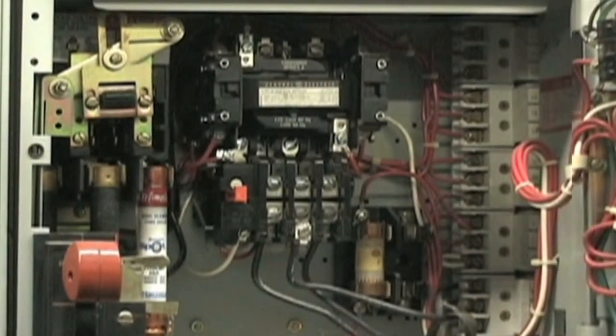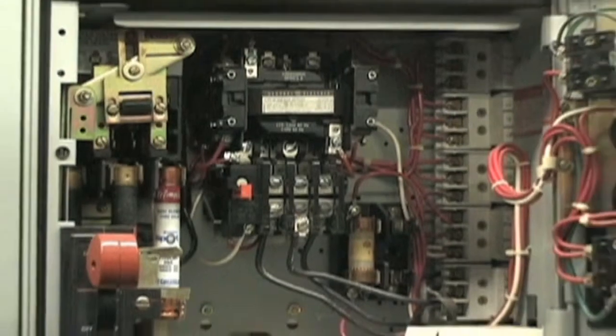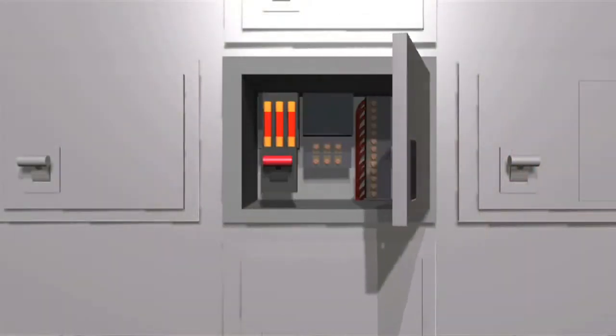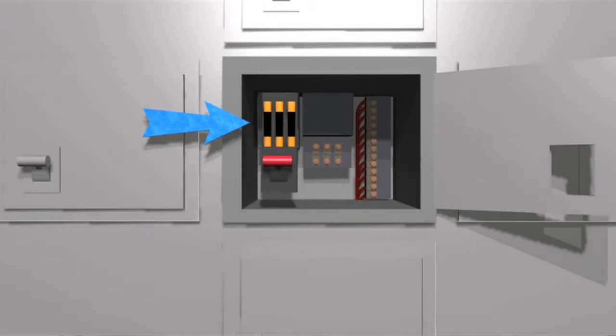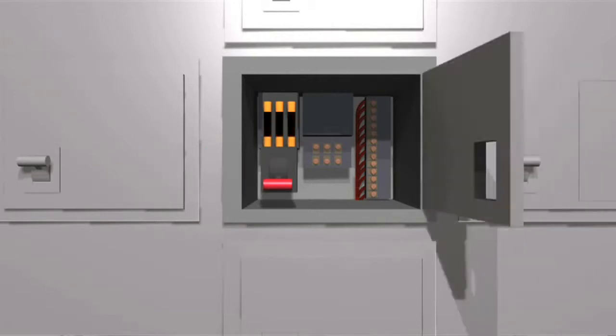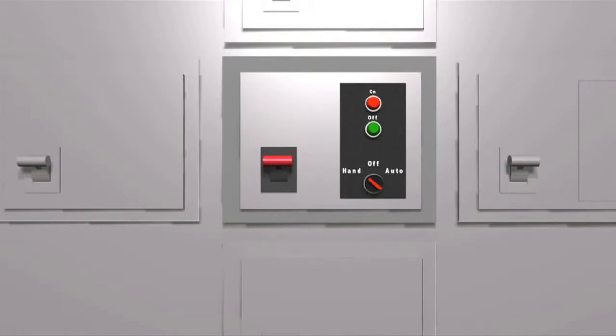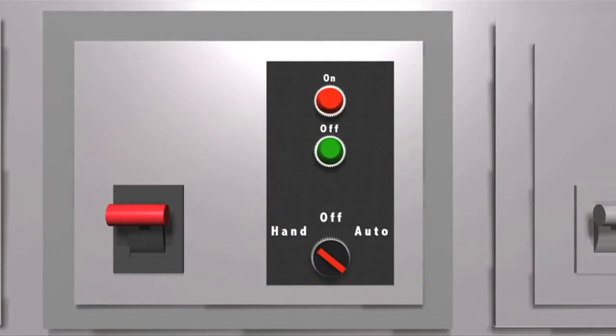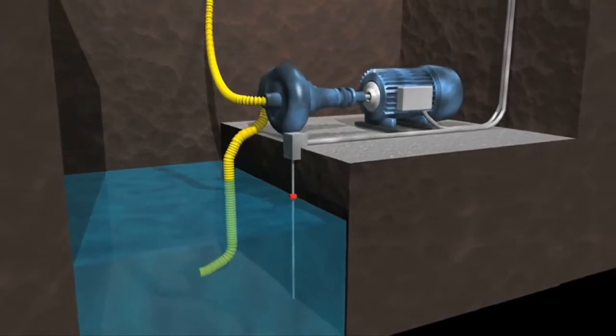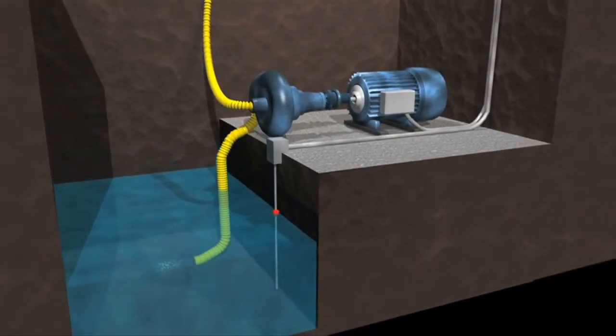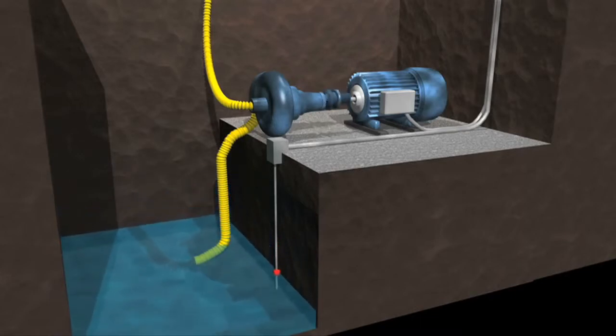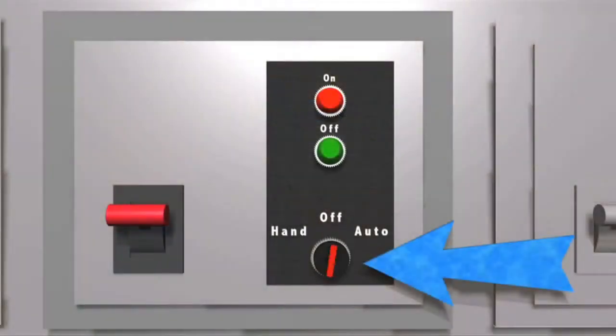For the purpose of electrical distribution, we only need to focus on a few components that relate specifically to the electrical. Each bucket has a disconnect switch and a breaker. The breaker is designed to trip if the power exceeds the recommended setting. The disconnect switch is there to manually turn off the power to the motor. There is also a combination motor starter. These consist of the same disconnect switch and breaker, but also has two other features. It has a start-stop switch to manually turn the motor on and off. It also has a hand-off auto switch. When this switch is in the auto mode, it allows another source to control the motor. A good example of this would be a sump pump. A float switch that is switched on by rising water will control the sump pump. The motor will be turned off when water levels go down and reset the float switch to the off position. When this switch is in the hand position, the motor is always on.